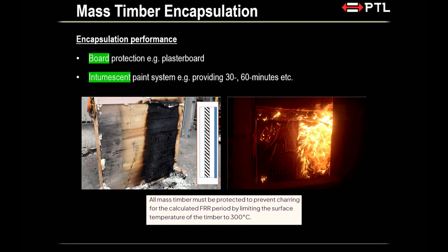Charring is happening. Now, if you wanted to prevent charring and therefore meet the encapsulation requirement, you need 2 layers, right? 2 layers of 13 mil. This side, no problem, right? There's no charring, right? There's no contribution of your timber to the fire, right?